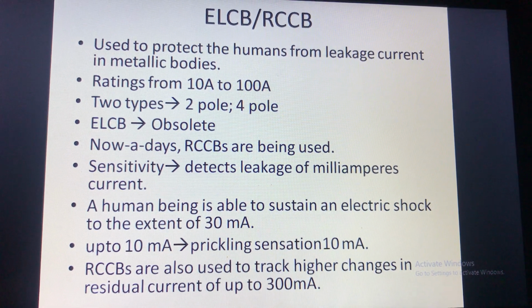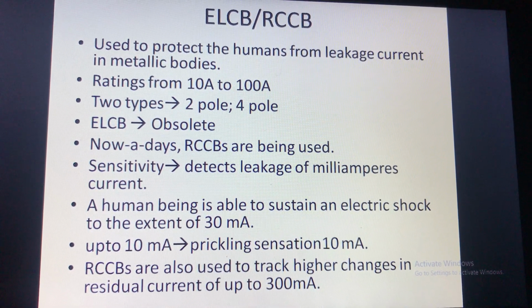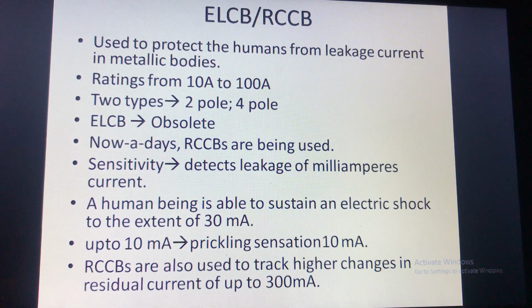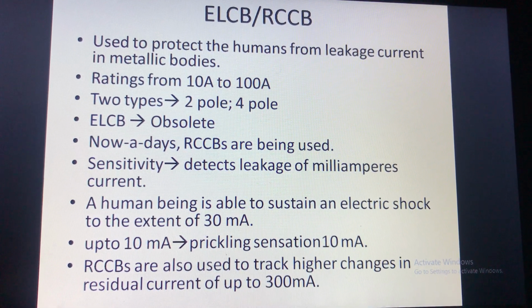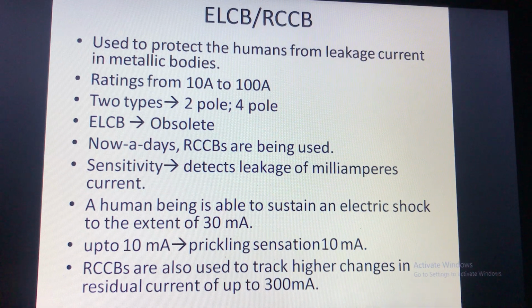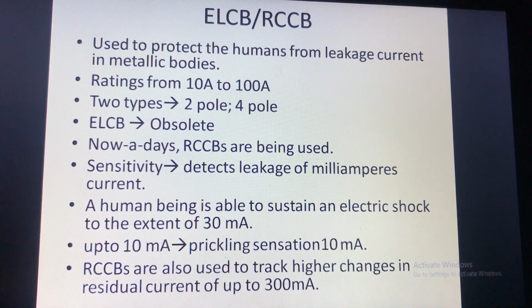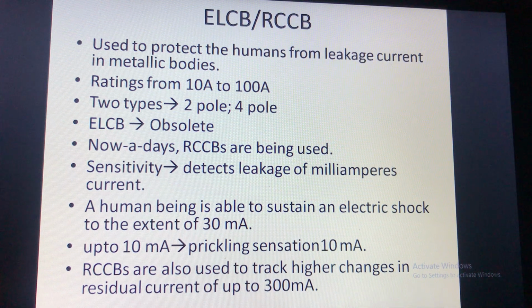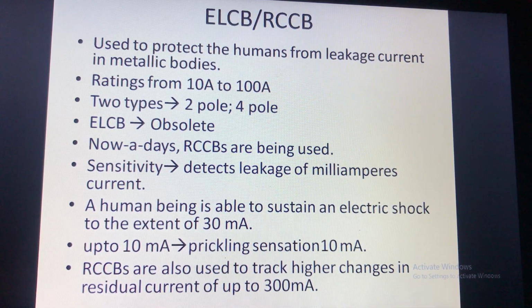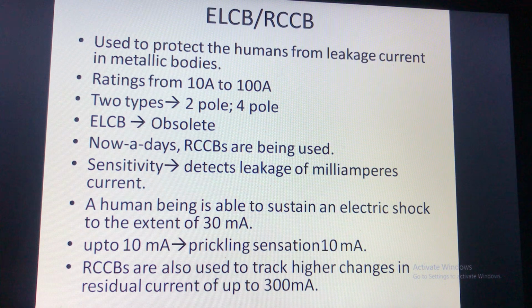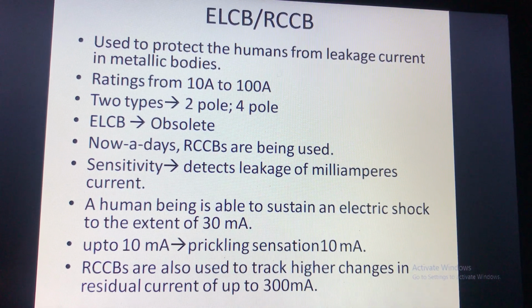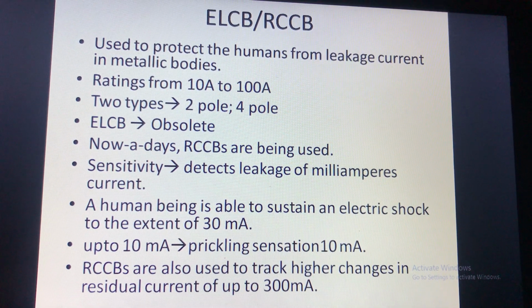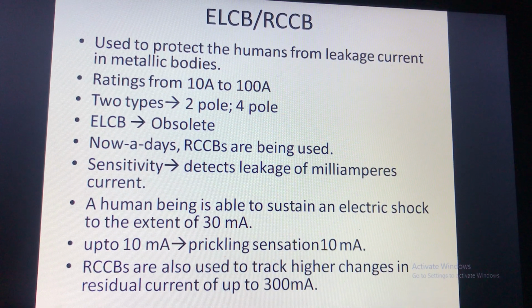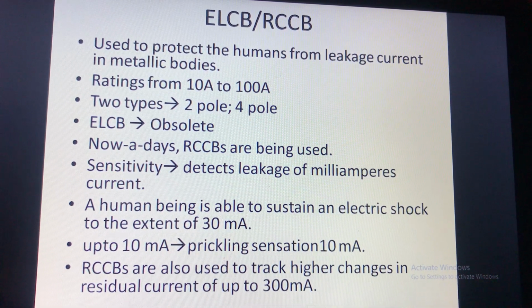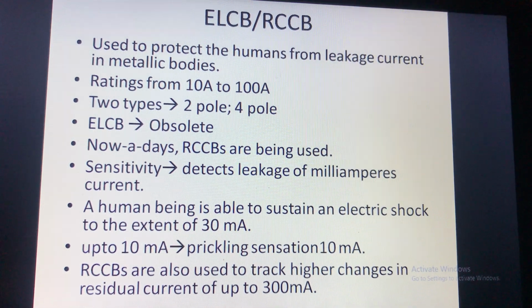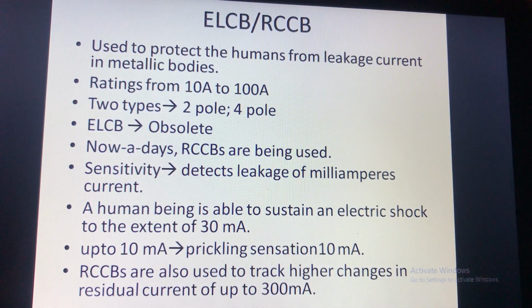They are available in ratings of 10 amperes to 100 amperes. 2-pole RCCBs are used for single-phase circuits and 4-pole are for 3-phase circuits. They can detect leakages of milliampere currents. As human beings can sustain an electric shock up to the extent of 30 milliamperes, up to 10 milliamperes only a prickling sensation they may evoke, but after 30 milliamperes it may lead to serious shocks. So RCCBs are used to track these higher changes in residual currents up to 300 milliamperes.